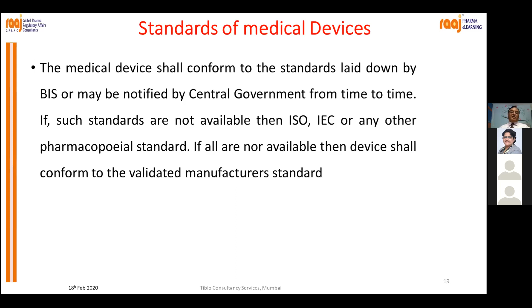So first one is BIS, another one is any standard notified by the central government. If both of them are not there, then ISO standard or IEC standard or pharmacopoeia standard. If there is no BIS, central government, ISO, IEC or pharmacopoeia standard, then the manufacturer's validated standard has to be complied with. Right. So this is, in a nutshell, how it will be regulated.